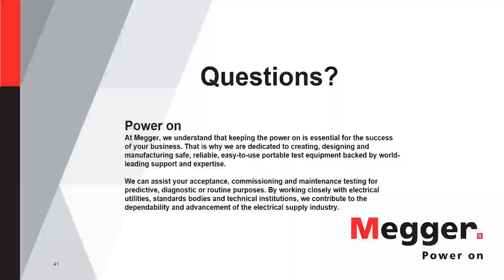So yeah, on this one, you would have to first fully charge the battery back up, and then you want to equalize it once again, and the standard requires you to do it 72 hours before performing the testing. And I'll even mention on this one, Clay, because you want to give every cell an equal starting point. What happened is some cells might have pulled down a little bit more than the others, so you'd rather equalize them all again. And same thing if you went through a test and had to jumper out cells and replace them eventually, you'd want to recharge, equalize, and perform another test.